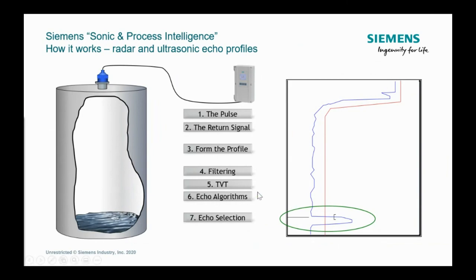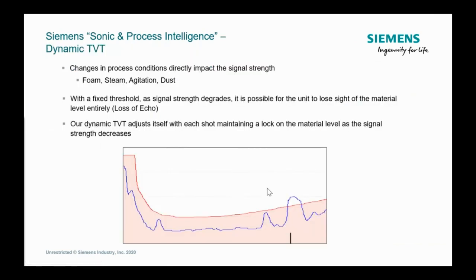The key thing here is this TVT, or time-varying threshold, is calculated each and every time it makes a measurement. As opposed to some of the other instruments out there that have a fixed signal reference line, what the Siemens instrument will do is recalculate that TVT and always try to optimize to changing process conditions. That could be agitation, some bubbling, or dust or foam or something that's interfering with the signal that will degrade the signal. So what the instrument's always trying to do is optimize that TVT to stay locked onto what it believes the echo to be. As a result, maybe the echo degrades and it adjusts the TVT down to catch it. And then as the signal gets stronger, it's going to adjust that TVT back up.